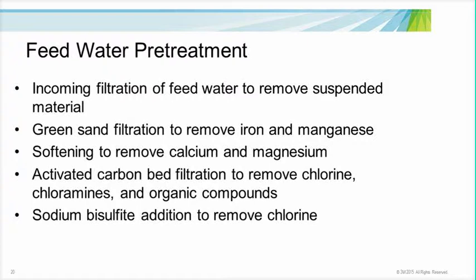Depending on the geographical location, the next stage of green sand or softening is used to reduce total dissolved solids and scaling impurities. For example, in the Northeast it is common to experience a high iron content in feed water. For removal, a green sand pretreatment is commonly implemented into the water system design. In the Southwest and Southeast, however, high calcium and magnesium content is common in municipal water systems, and a softening technology is commonplace in pretreatment. Carbon beds are commonplace prior to principal treatment as they further remove chlorine and total organic carbon through adsorption. Alternate dechlorination methods include chemical treatment with sodium bisulfite, for example.